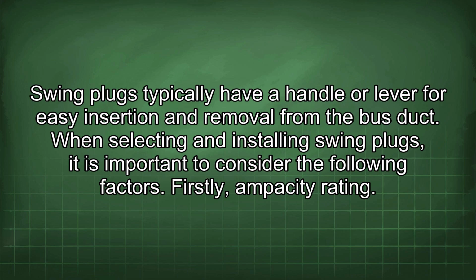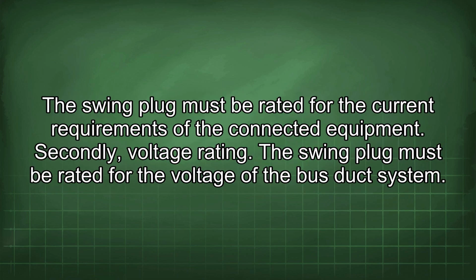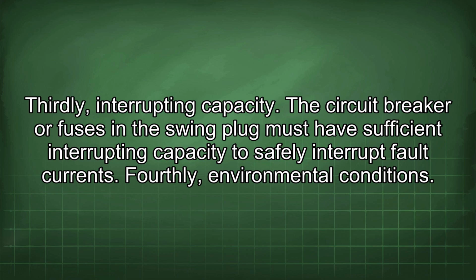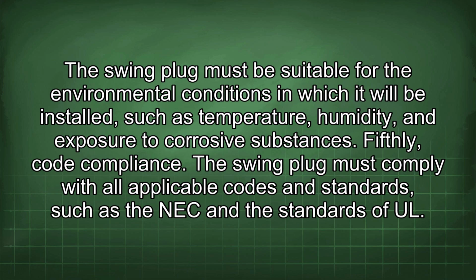When selecting and installing swing plugs, it is important to consider the following factors. Firstly, ampacity rating. The swing plug must be rated for the current requirements of the connected equipment. Secondly, voltage rating. The swing plug must be rated for the voltage of the bus duct system. Thirdly, interrupting capacity. The circuit breaker or fuses in the swing plug must have sufficient interrupting capacity to safely interrupt fault currents. Fourthly, environmental conditions. The swing plug must be suitable for the environmental conditions in which it will be installed, such as temperature, humidity, and exposure to corrosive substances.